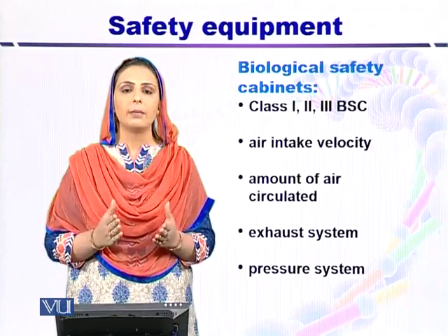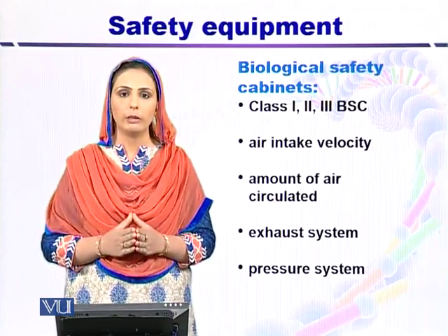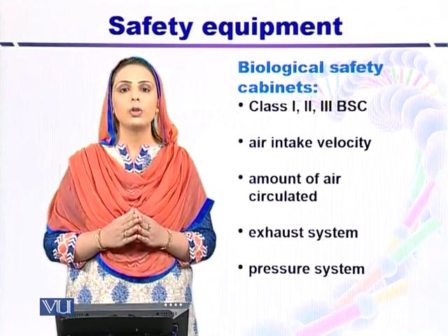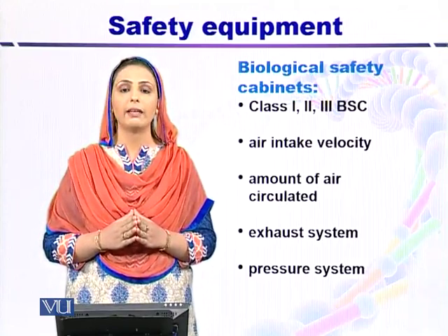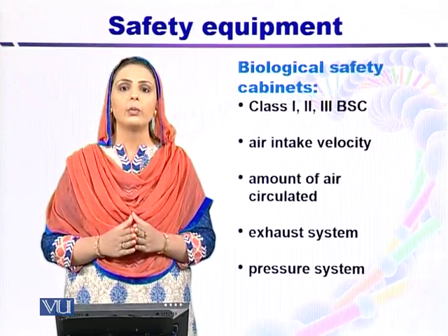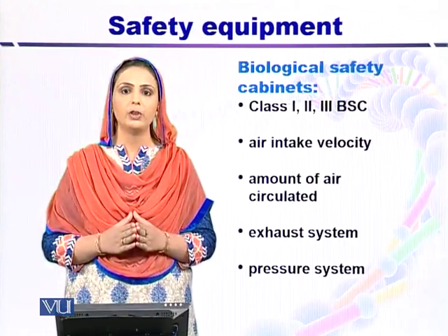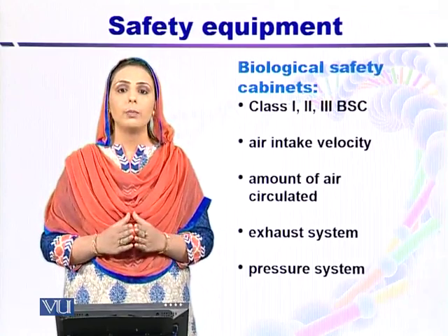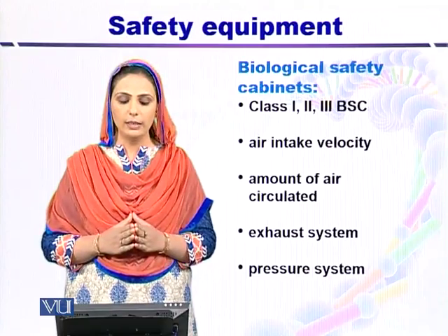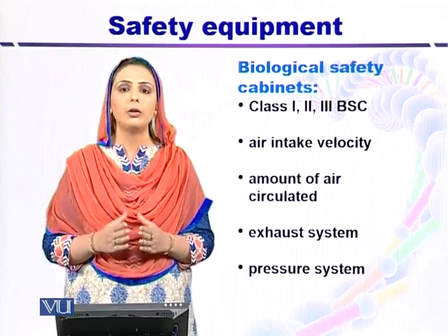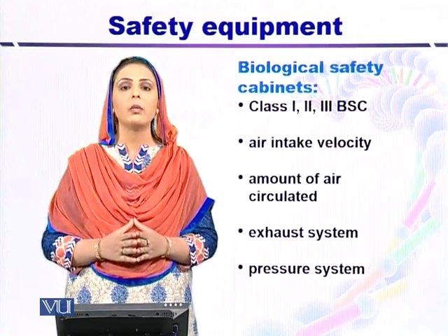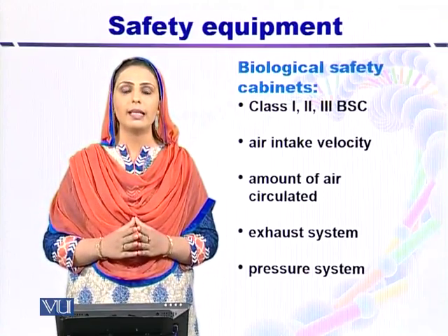Now, biosafety cabinets, why is it so important? Because they not only protect the workers, but they also protect the lab environment and the working material. Now, how can we decide which type of biosafety cabinet should be used? It depends upon certain parameters like air intake velocity.